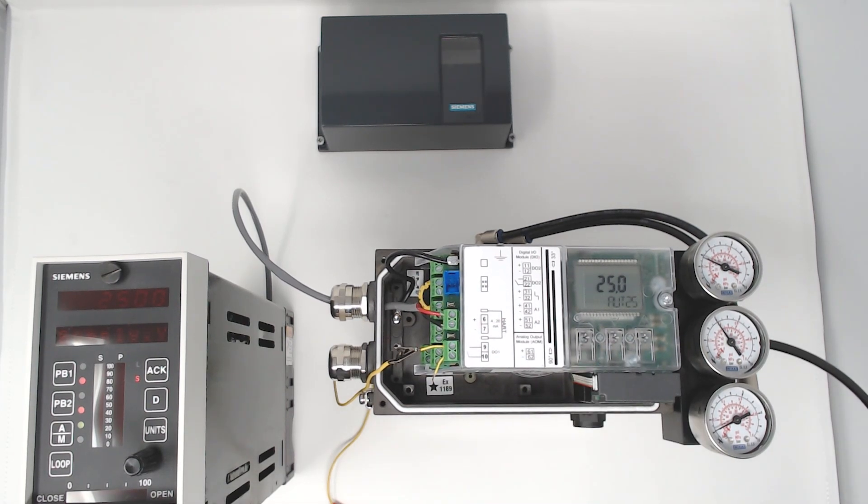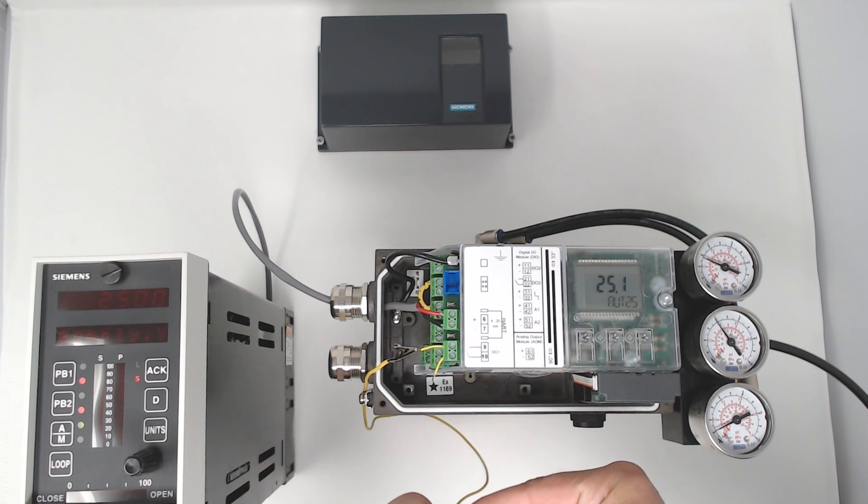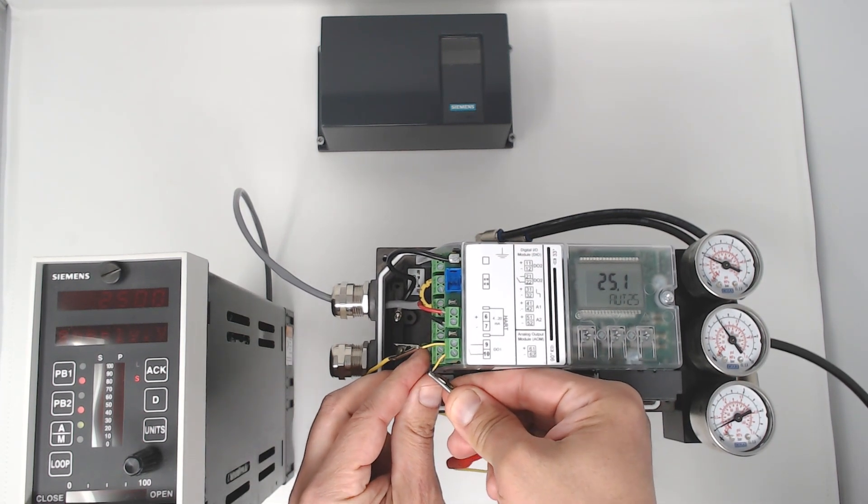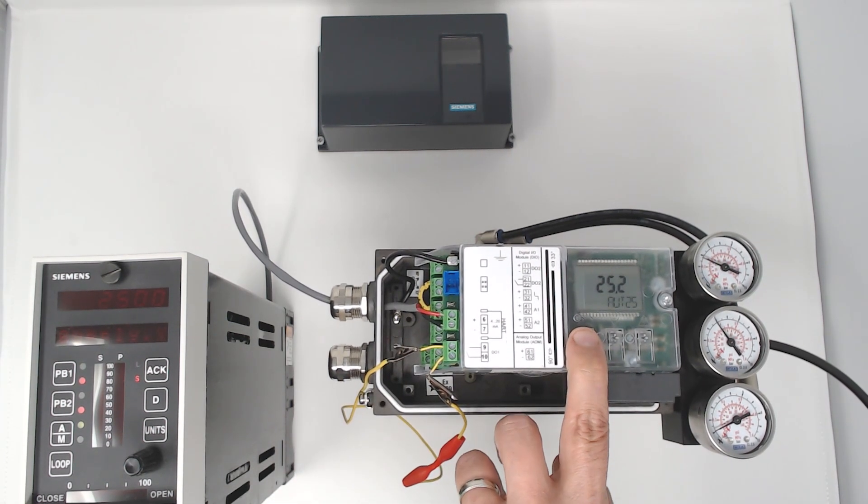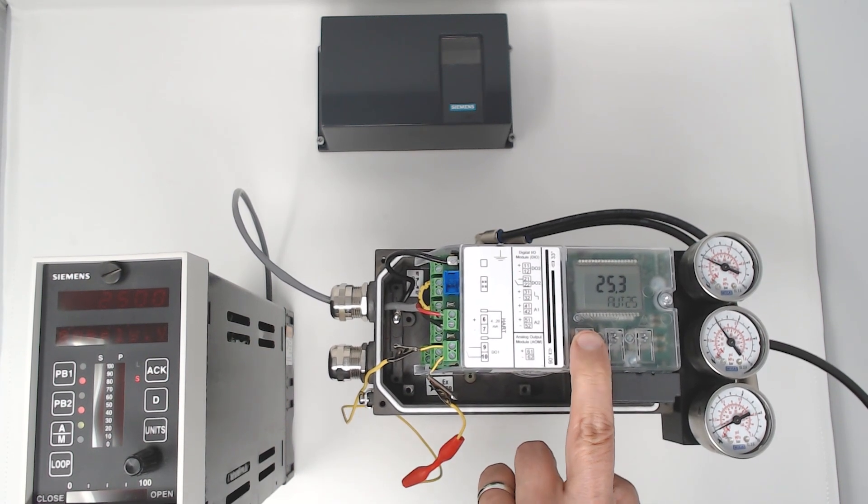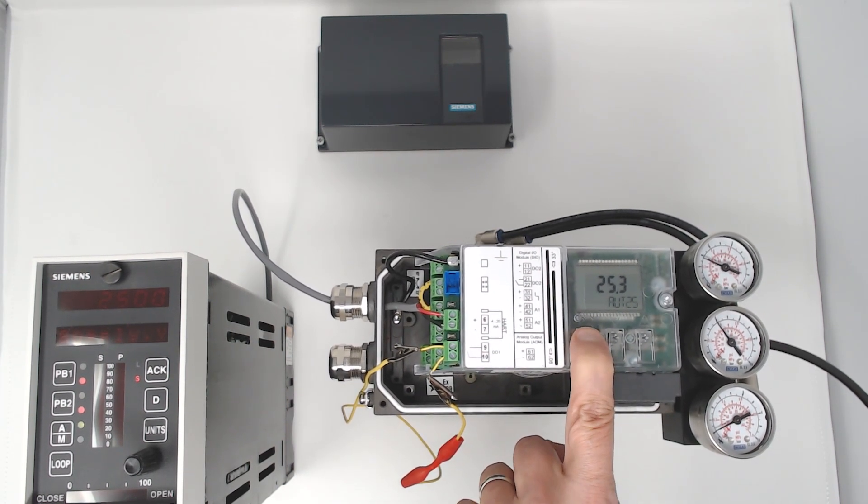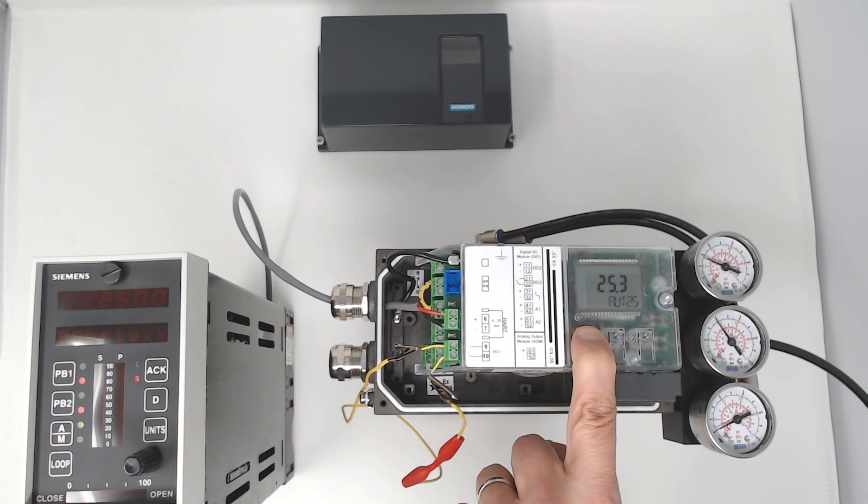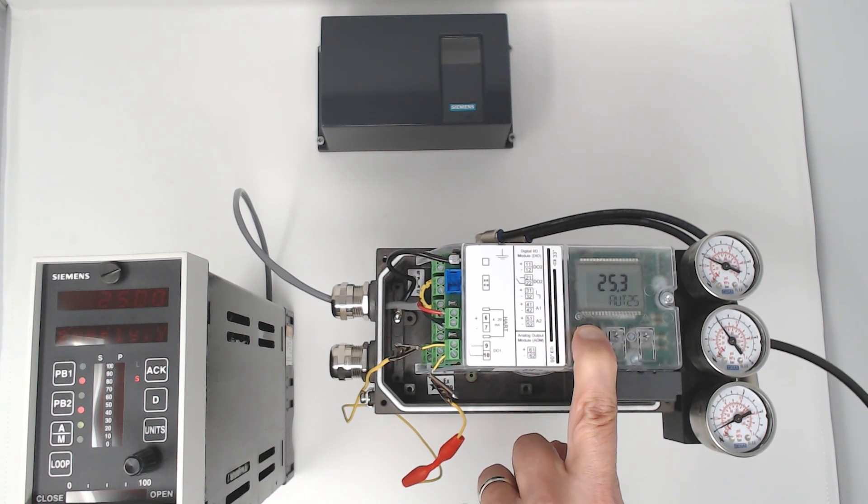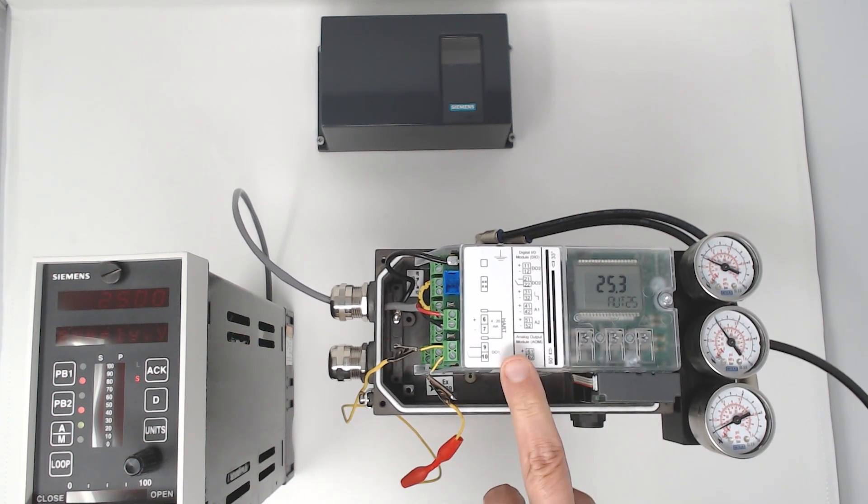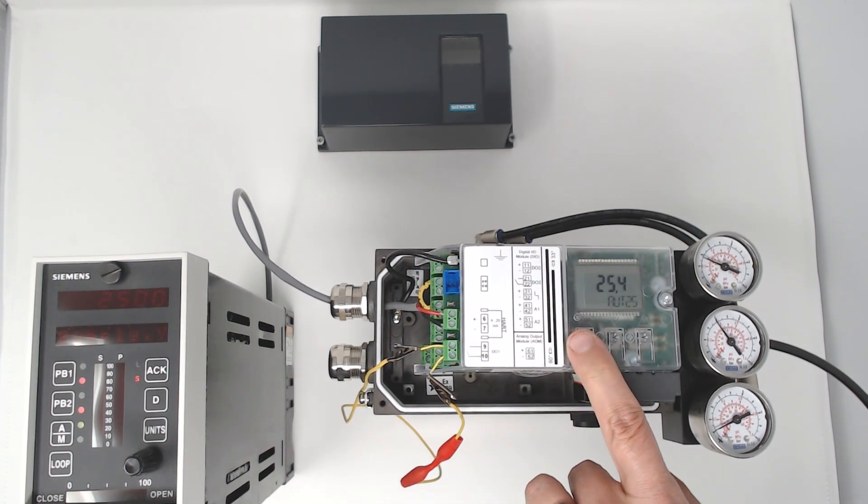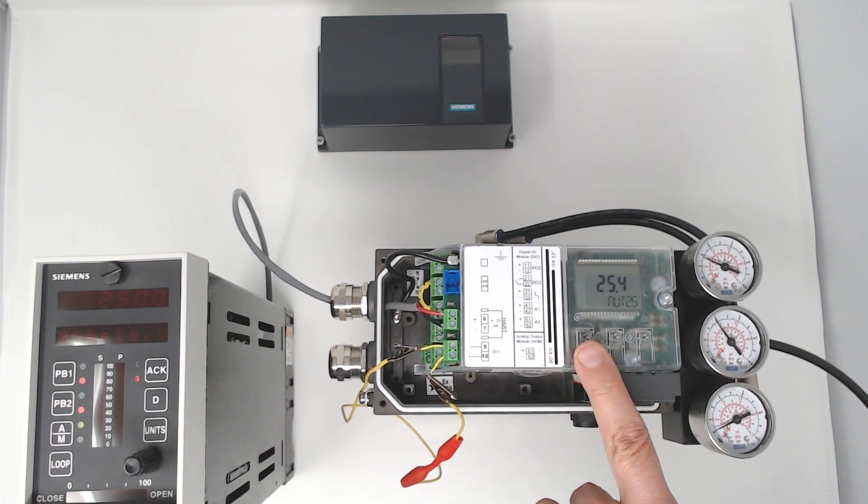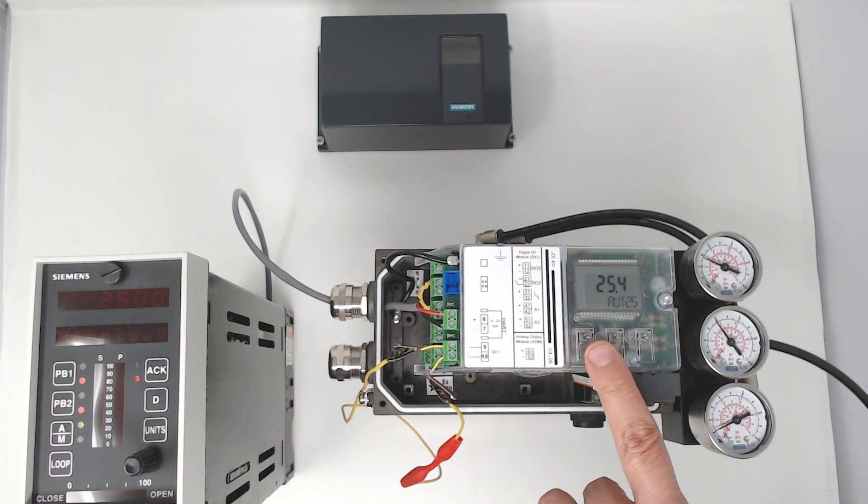So now I'm going to short out terminals 9 and 10 with my jumper. And you can see I'm pressing the button, but it's not going into manual mode. I'm pressing and holding the button, and I can't gain access to the configuration. This is a nice feature for customers that are a little bit concerned of the accessibility that's offered with the PS2 with the local push buttons and display.